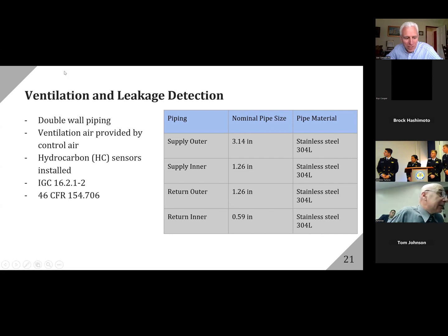Okay, excellent presentation, guys. I'm very pleased to see that you really took a full spectrum on the propulsion engine. Three questions. First one is, since you're going to be using LPG as a fuel, is there any purge provision before starting that engine with gas? The use of gaseous fuels is kind of a new thing to the world of propulsion diesels, and there have been problems with the exhaust, basically the flue gas path, having pockets of gas in there. So did the engine manufacturer talk about this at all to you, or did they show any literature? Usually we worry about putting in either a time delay on start where you can crank the engine long enough to purge the exhaust path, or using a purge fan. So was any of that mentioned by MAN or no?